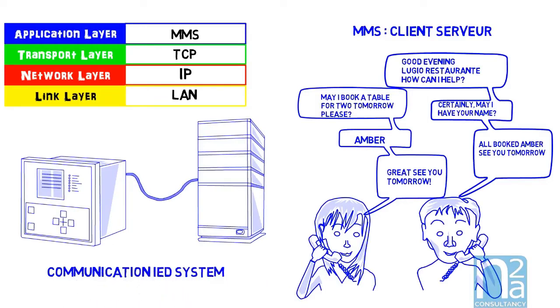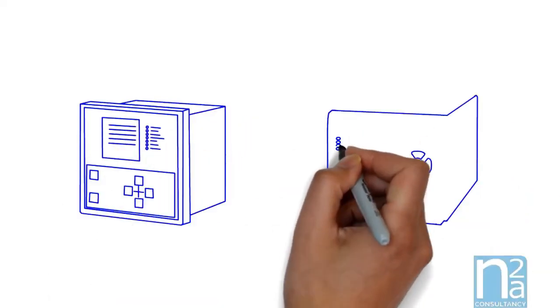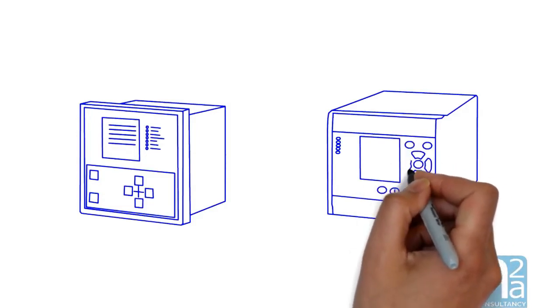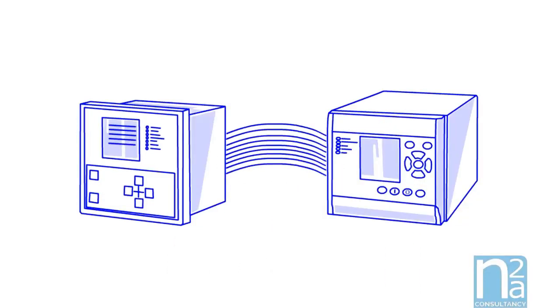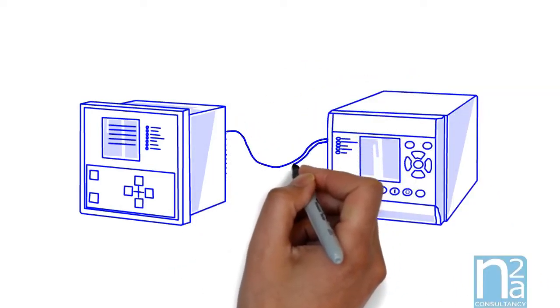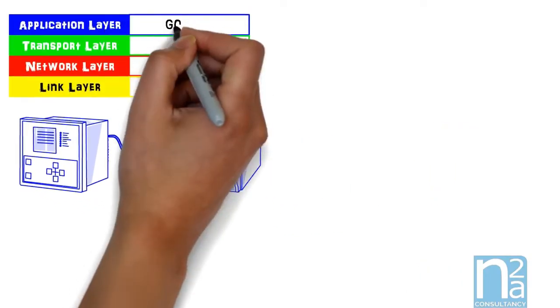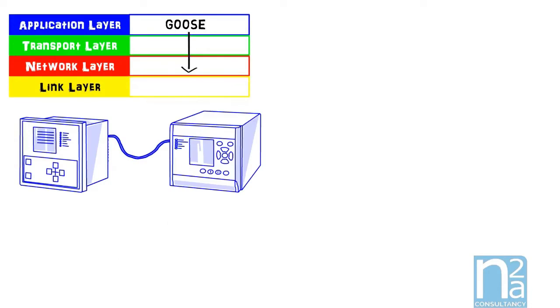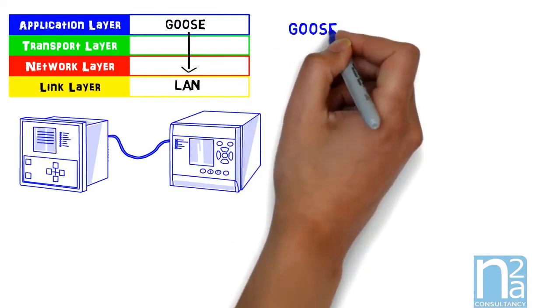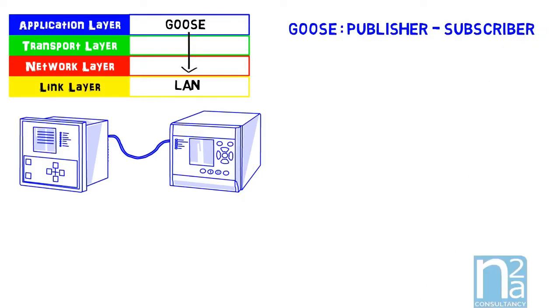The second communication breakthrough of IEC 61850 is the GOOSE message. GOOSE messages stand for Generic Object-Oriented Substation Event. They are used to send urgent messages between IEDs, like tripping and blocking, and replace hard wiring needed for selective interlocking schemes. GOOSE message application is directly linked to the link layer to deliver very quick information in less than 4 milliseconds. It is what we call a real-time protocol. It is based on a mechanism called publisher-subscriber. The message is broadcast over the local network to all devices who are listening.